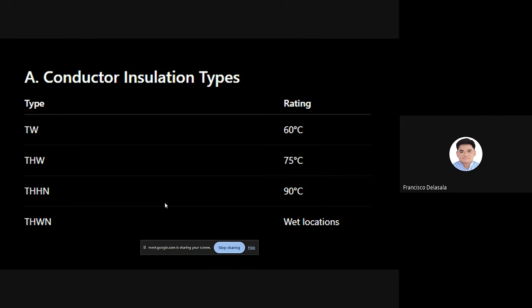We have TW, wala po itong H, so this is 60 degrees Celsius, ito ang kanyang maximum temperature rating. Then you have THW, this is 75 degrees Celsius. May isang H; pag dalawa yung H, that will be 90 degrees, which is THHN. Then if wala pong W, this type of wire is not suitable for wet location. For example, itong THHN, this is not for wet location. Yung N naman, this is the nylon coated or nylon jacketed, ibig sabihin aside from the insulation itself, meron pa siyang parang transparent membrane na nagpo-protect sa ating wire.